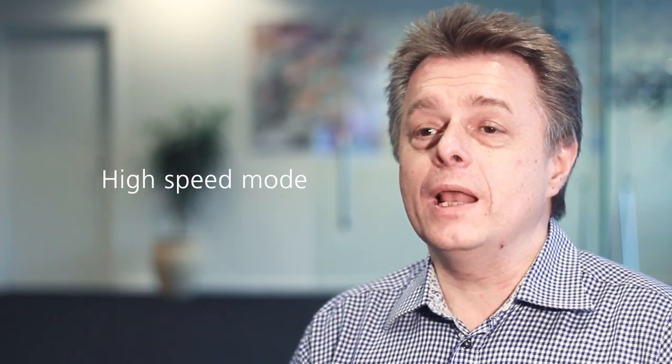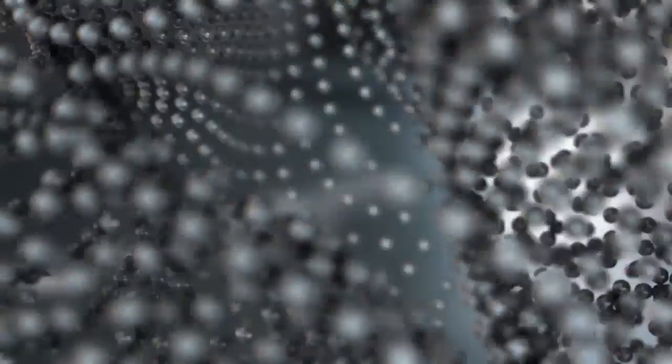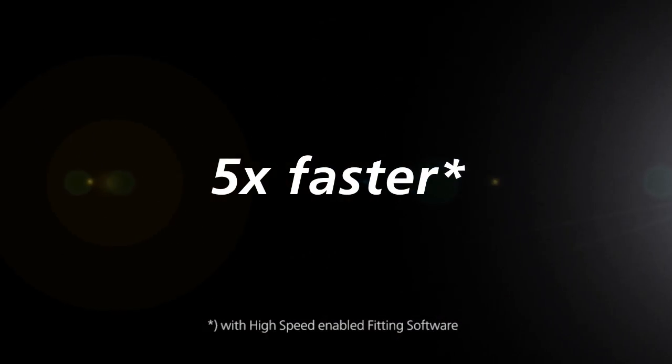Communication takes time. Time increase has a negative impact on the fitting experience, and this is exactly why HI-PRO 2 has a high-speed mode. This mode allows high-speed mode enabled fitting software to make HI-PRO 2 communicate with hearing instruments three to five times faster than a HI-PRO USB.